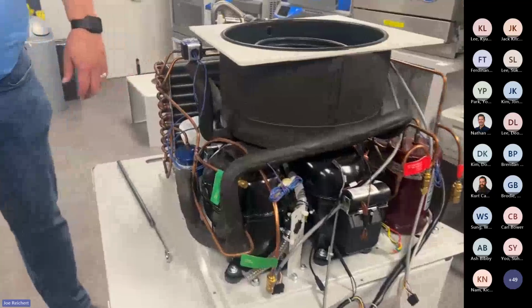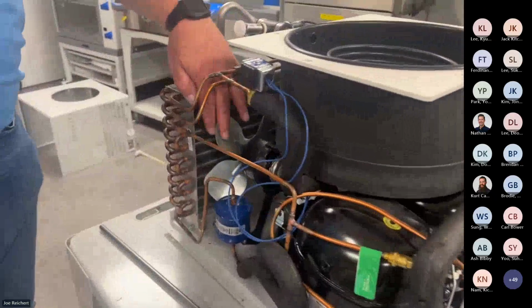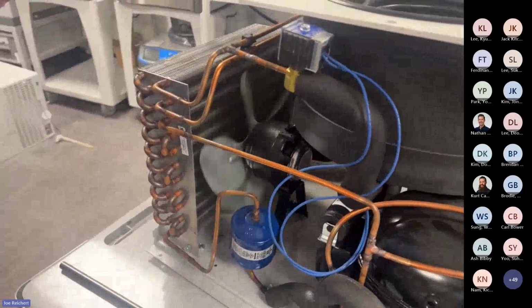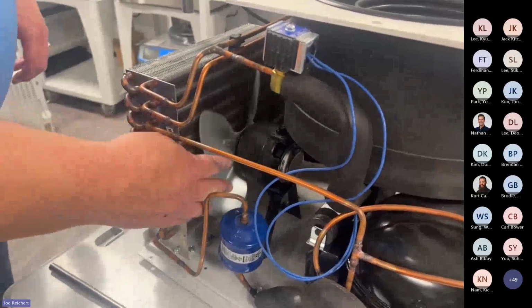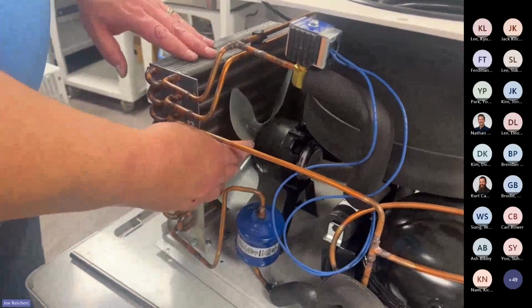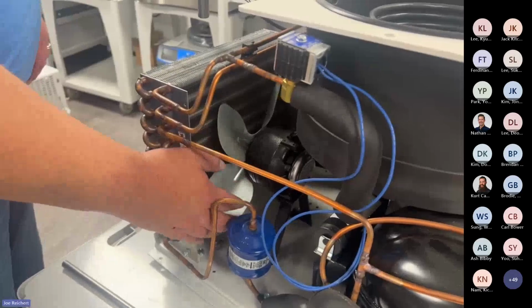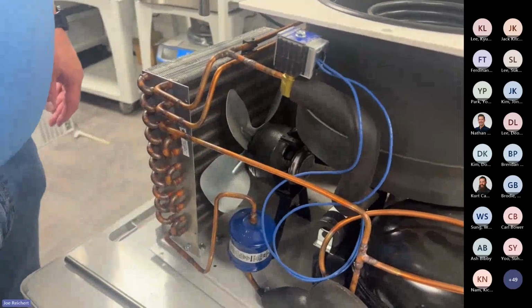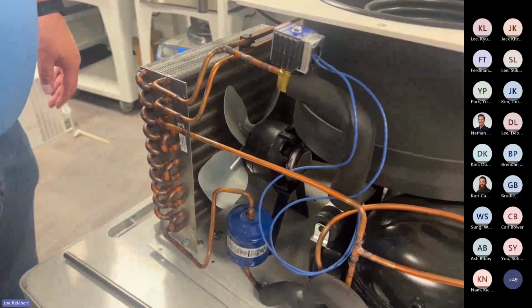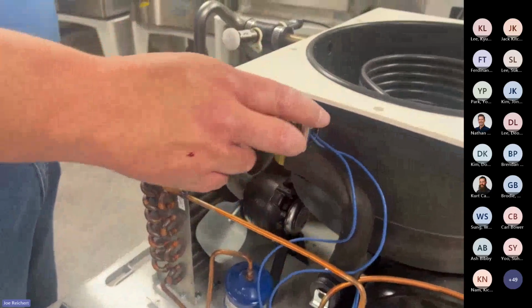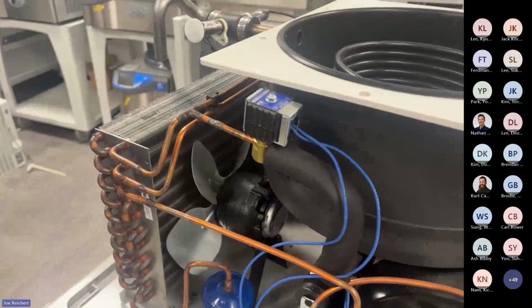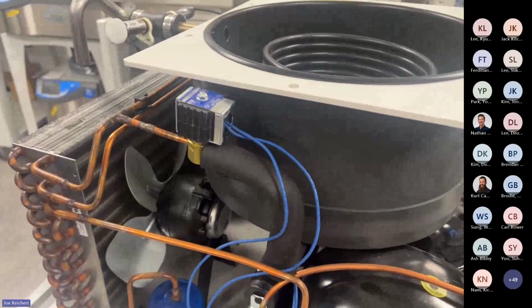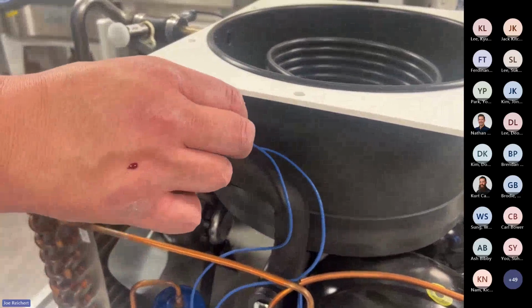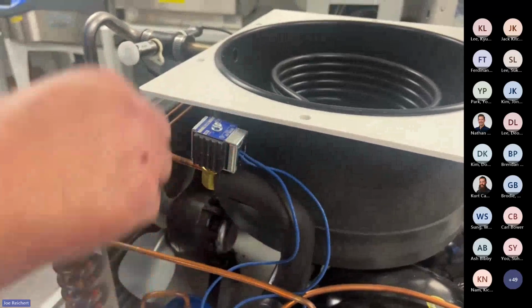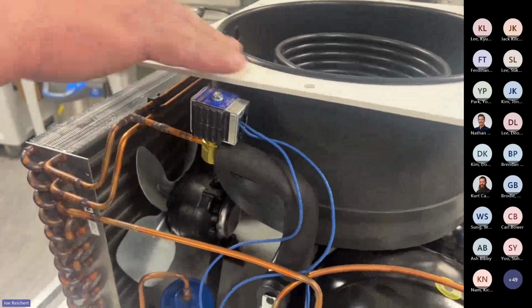Now inside the machine, we can see our cooling fan. I've seen cooling fans get stuck up in insulation, or maybe even getting too close to the condenser itself. I've seen it hit that. Usually you'll hear a wire getting hit by that fan blade. This is our defrost valve after we made the update in 2016, 2017 to our new style units. Every unit now has a defrost valve, a hot gas bypass so that we can melt ice off of our collector easier.